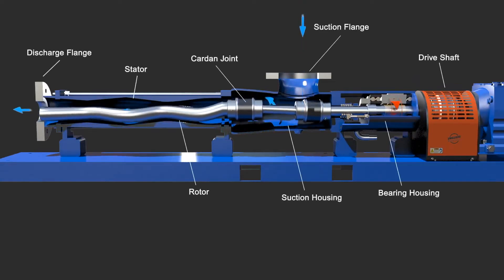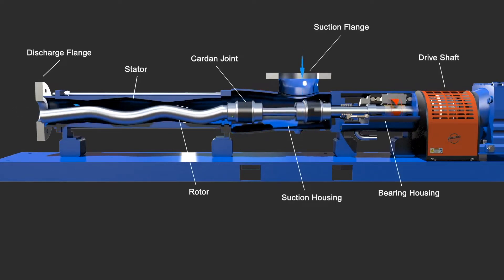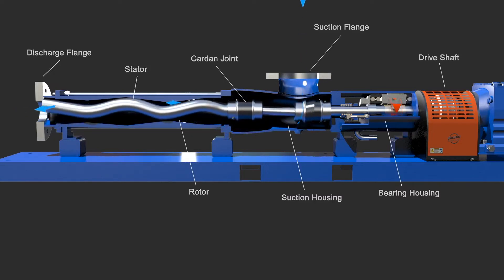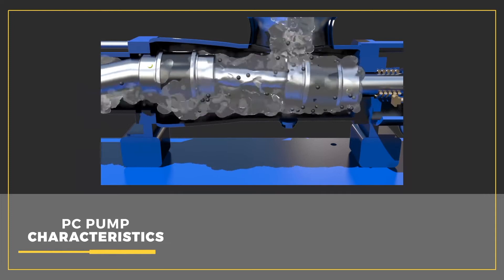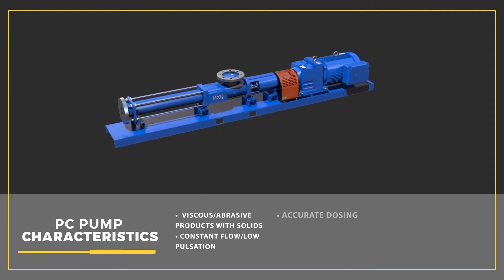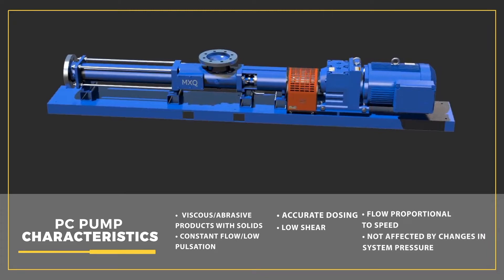The MXQ progressive cavity pump is 100% fit, form, and function Bornemann equivalent. The main components are driveshaft, bearing housing, suction flange, suction housing, Cardan joints, rotor, stator, and discharge flange. The pump is capable of pumping abrasive or viscous products with solids up to 3 inches, maintains constant flow and low pulsation, and smaller models provide accurate dosing for chemical injection applications. It is ideal for shear-sensitive products, and pump flow is proportional to speed.